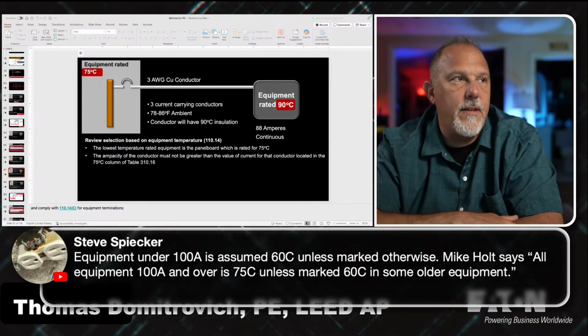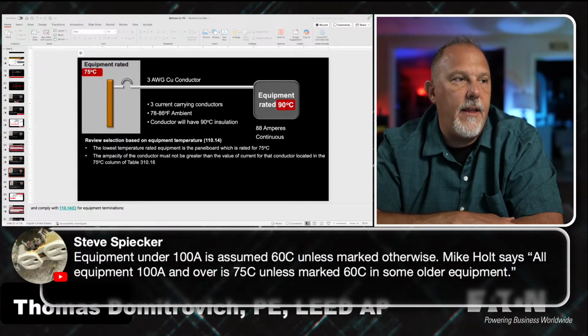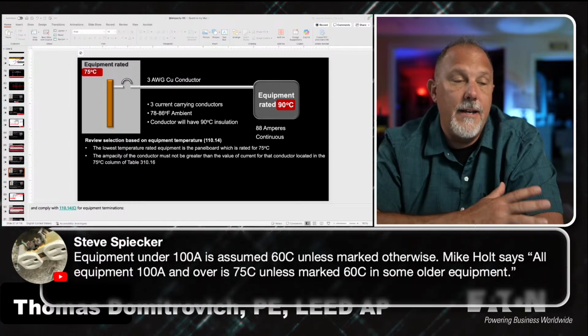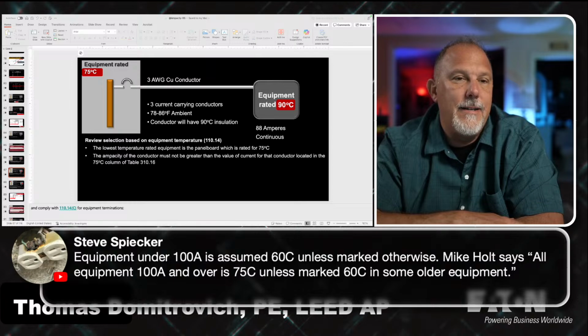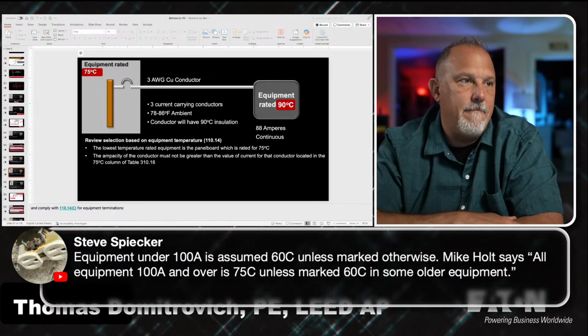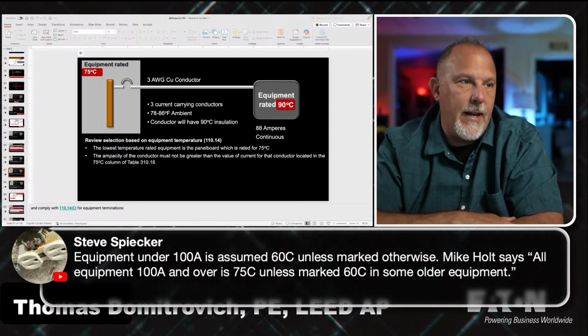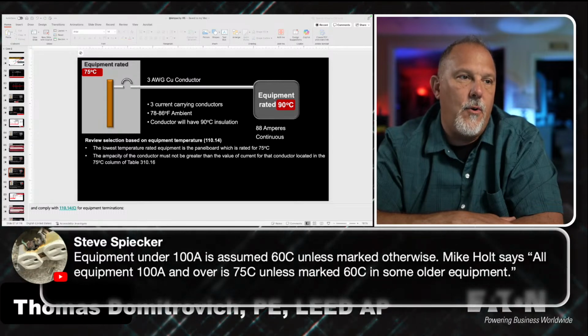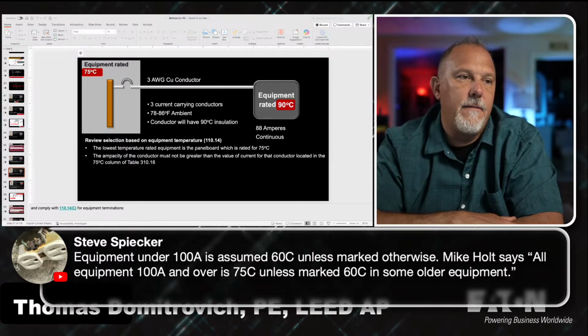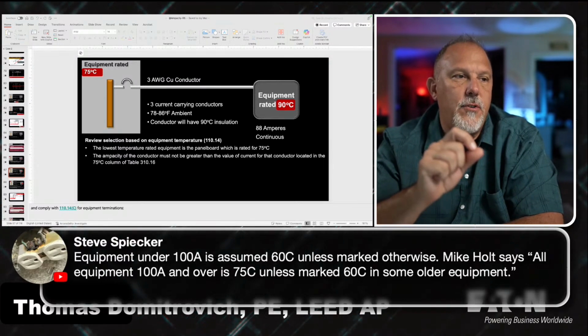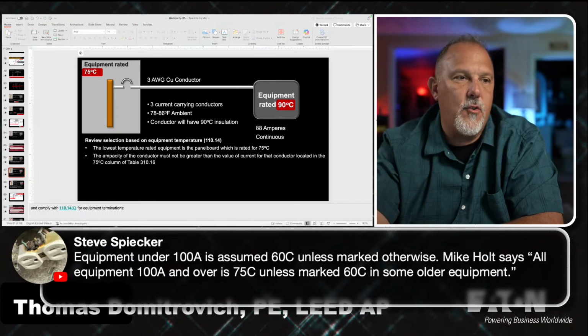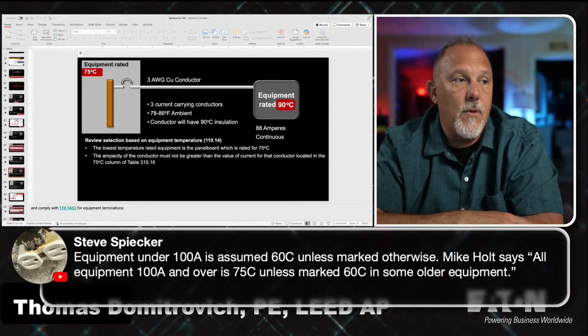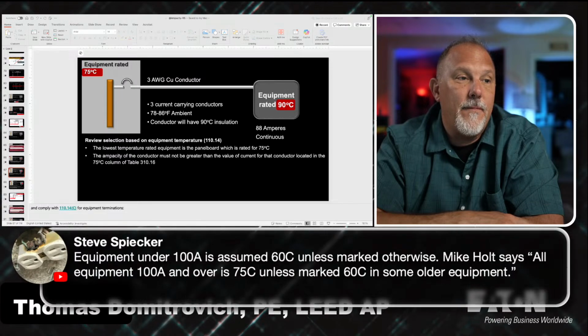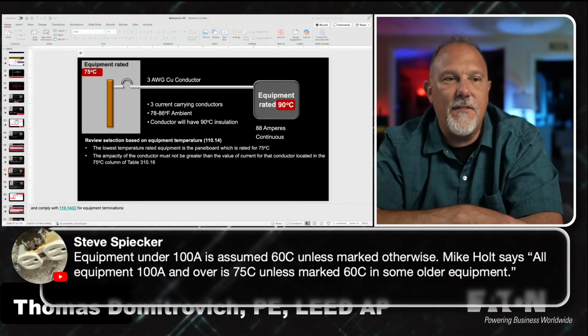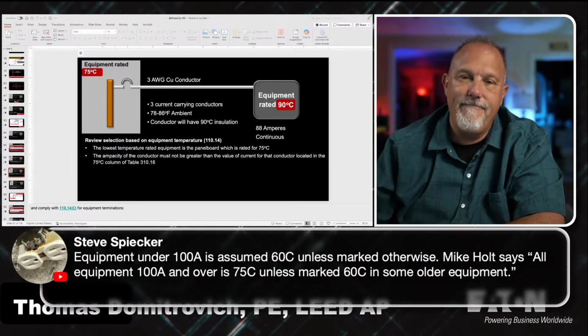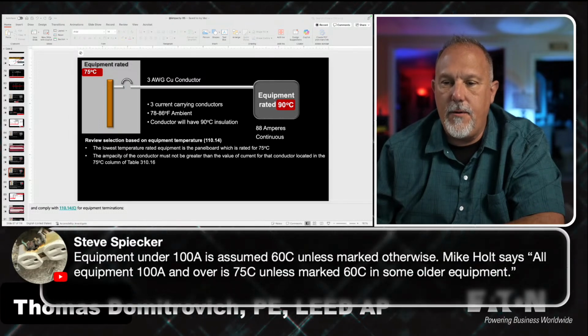But I'm not sure if I agree with 110.14(C)(1)(a)(3), conductors with higher temperature ratings if the equipment is listed. The conductor is 90 degrees C, the equipment is 90 degrees C. So it should say conductors with temperature ratings that are equal to or greater than. That's what it should say. Conductors with a temperature rating equal to or higher than the equipment, if the equipment is listed and identified for use with those conductors. Or conductors with any temperature rating, if the equipment is listed and identified for use with those conductors. Anyway, it's semantics, but I know we know what you know and you know.